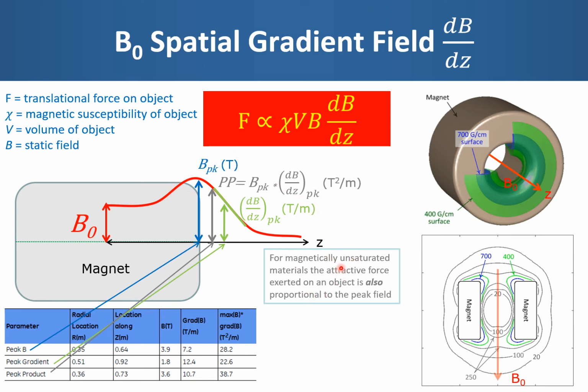The ferromagnetic attraction force is proportional to the magnetic susceptibility of the object, the volume of the object, the static field if the object is magnetically unsaturated, and most importantly, the rate of change of the field with distance from the magnet. MRI manufacturers are now required to provide plots of this spatial gradient with position, and here we can see that the highest spatial field gradients happen to be nearest the magnet itself.